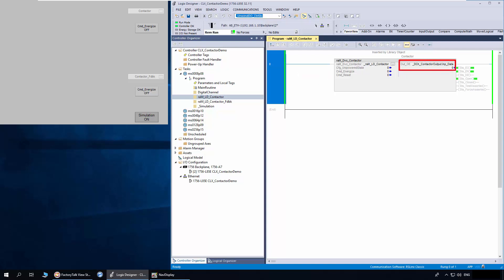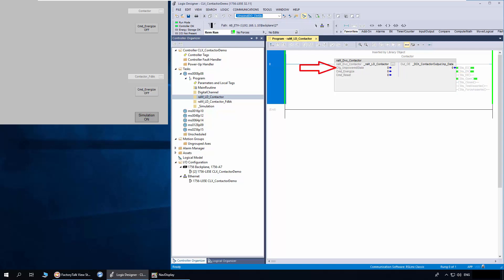In this demo application, the output is connected to a digital channel. The status bits can be used in the user logic. The unpowered state parameter defines the contactor state — whether open or closed — when the output is off. The configuration parameters can be set from the HMI faceplate or logic.